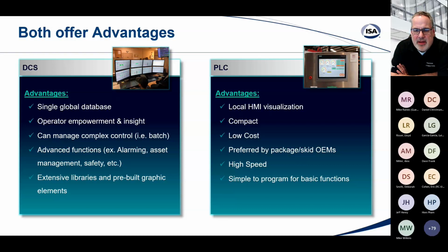The operator empowerment and insights. So again, the DCS handling more information, it provides and reduces the need for engineering interference. Once the unit is up and running, it gives the operator really a lot of availability to adjust set points and do things without having to really call in the engineering group to do any reprogramming. Again, I mentioned it can manage complex controls such as batch. It has typically advanced functions. We've been talking a little bit about alarming, asset management, even integrated safety. And again, extensive libraries and pre-built graphic elements I mentioned before.